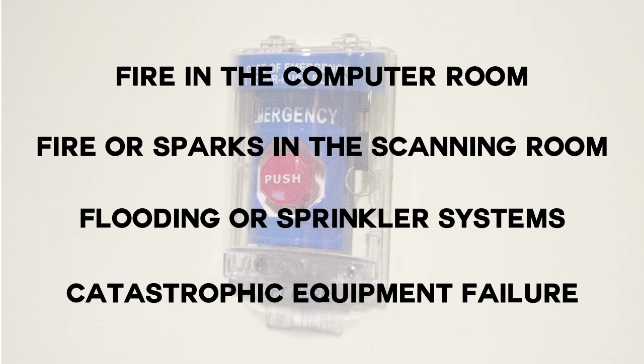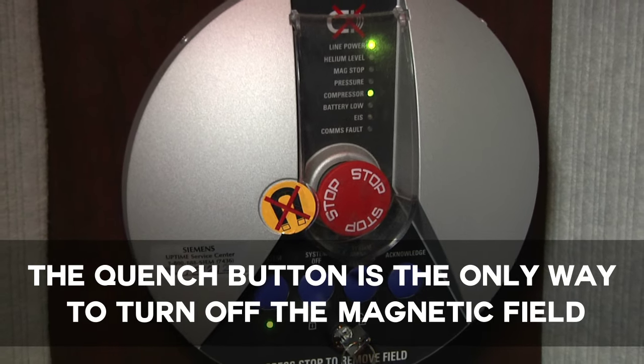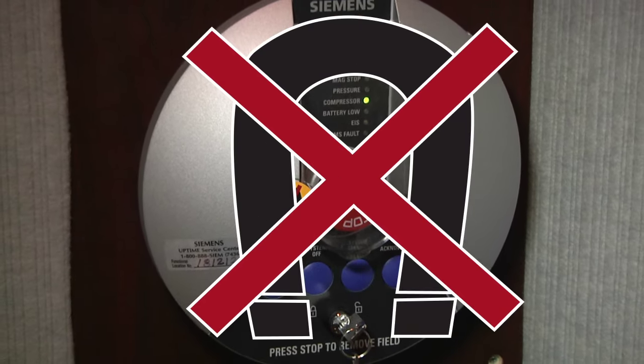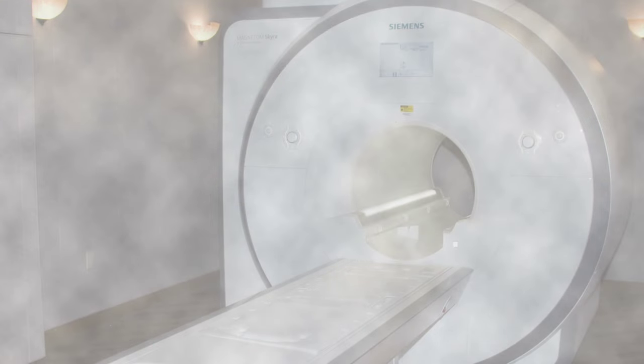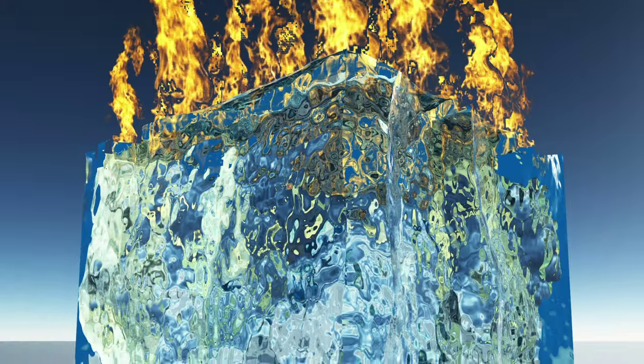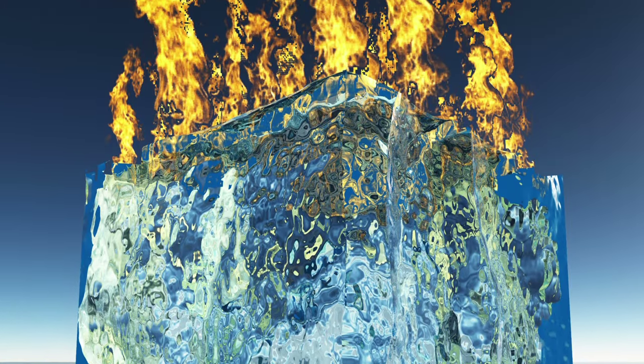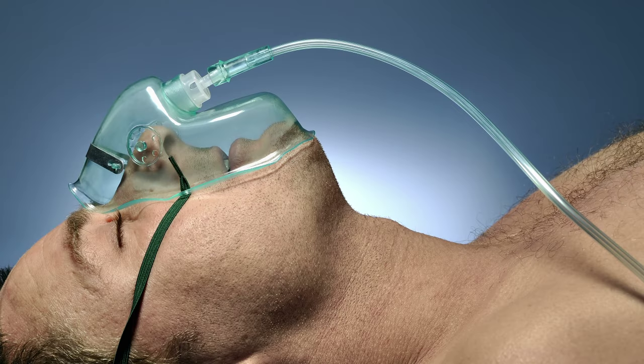The other emergency button is the quench button. This will cause a collapse of the superconductive magnetic field within minutes. When a system is quenched, all of the cryogens discharge at once outside the building through vent pipes. If the pipes fail during a quench, frigid helium can discharge into the MRI room. Liquid helium is roughly 450 degrees below zero and can cause severe cold burns. Pressure in the room would increase dramatically and the oxygen would be depleted as the gas expands. Asphyxia would become a strong concern.